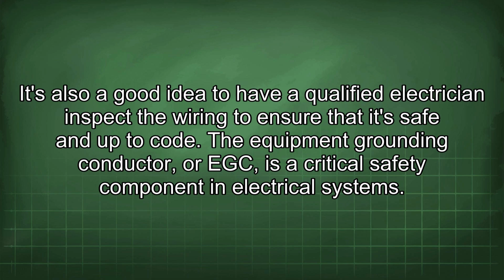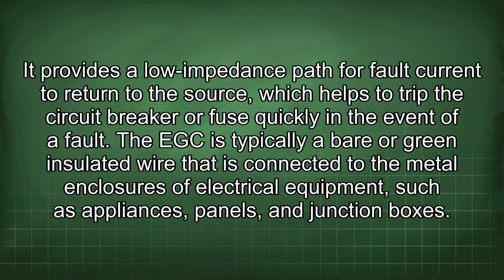The equipment grounding conductor, or EGC, is a critical safety component in electrical systems. It provides a low impedance path for fault current to return to the source, which helps to trip the circuit breaker or fuse quickly in the event of a fault. The EGC is typically a bare or green insulated wire that is connected to the metal enclosures of electrical equipment, such as appliances, panels, and junction boxes.